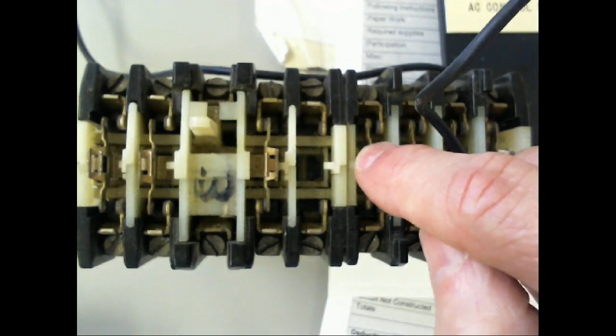So this relay right here, this control relay right here, has 1, 2, 3, 4, 5 - this one got tore off - 6, 7, 8 poles on it. So I could use my one solid state sensor to bring this guy in, and I could control 8 circuits with one solid state. So just about all your solid state sensors are probably going to have one contact. We do have some that are double throws, but they're all single poles. I haven't seen one that has multiple poles, multiple circuits that you control.